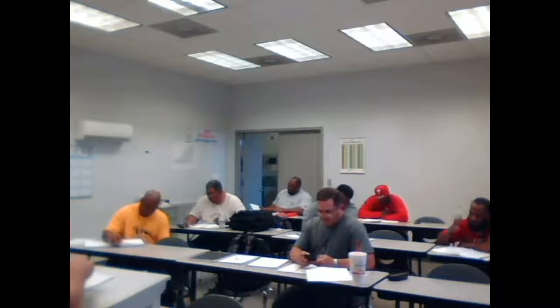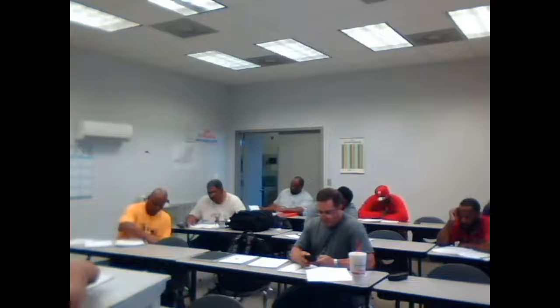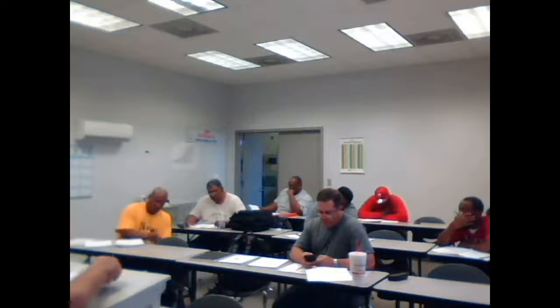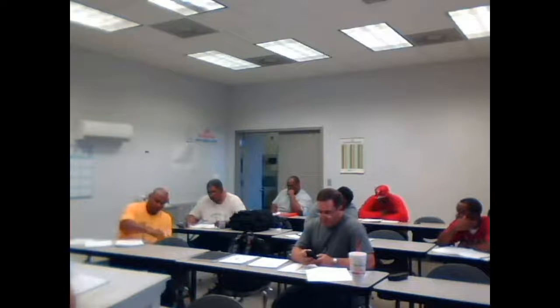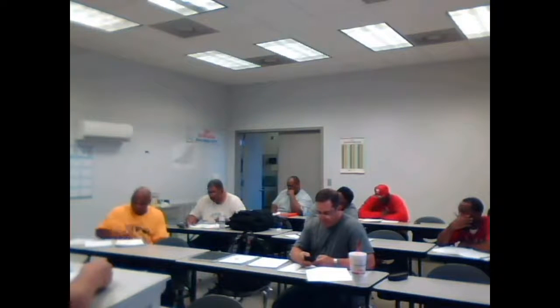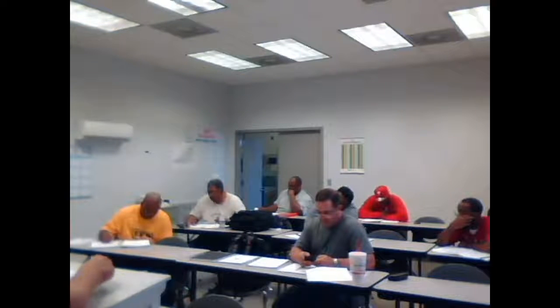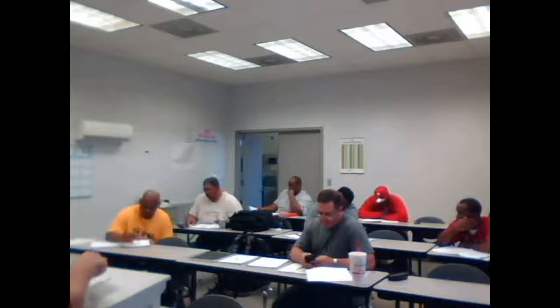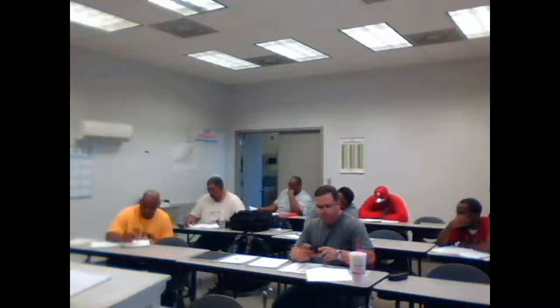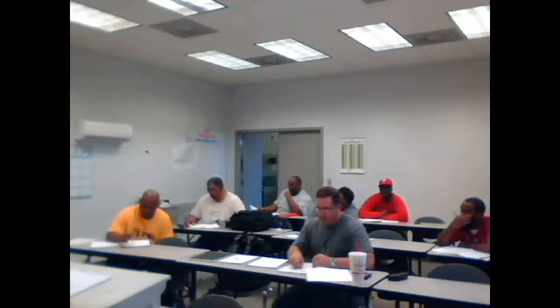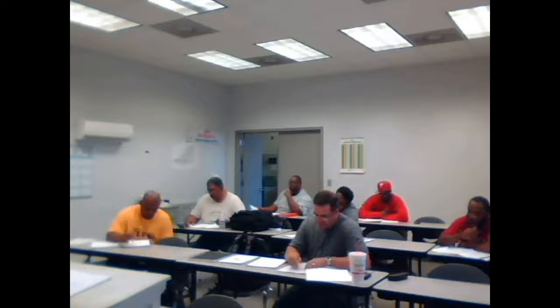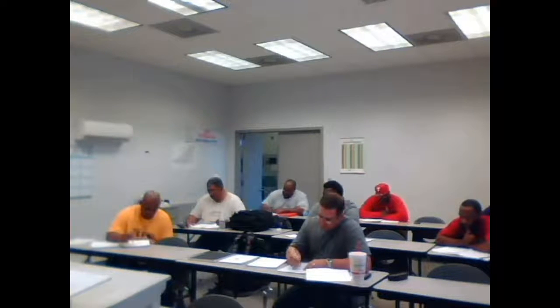They're telling us that the Y is energized, I believe, right? They're closed. I think that's what it said. The Y terminal at the thermostat is closed. And we've got power, or the blower motor wouldn't be running, probably. What would let the blower motor work and not the compressor and the condenser fan? Okay, the high pressure or the low pressure switch. Some of those are overloads y'all are talking about. The oil switch, right? What else?